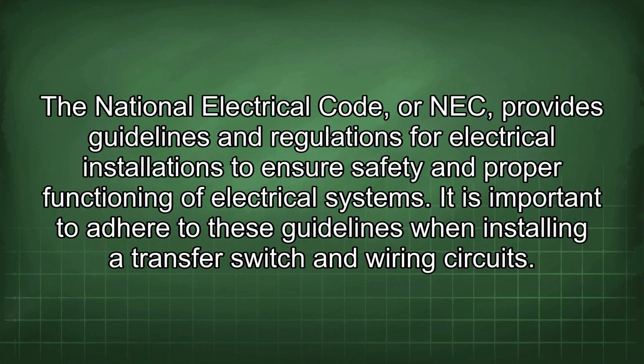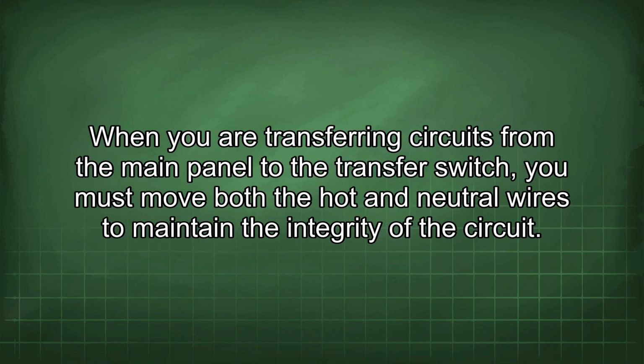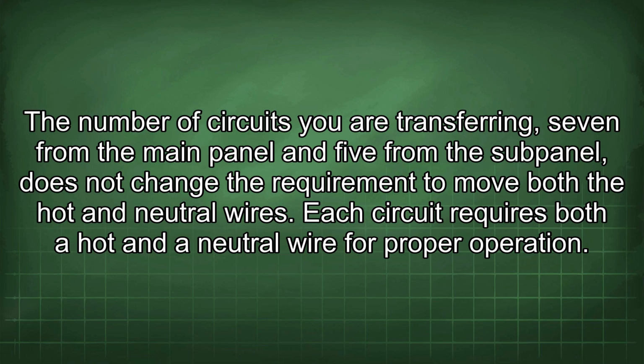The National Electrical Code, or NEC, provides guidelines and regulations for electrical installations to ensure safety and proper functioning of electrical systems. It is important to adhere to these guidelines when installing a transfer switch and wiring circuits. When you are transferring circuits from the main panel to the transfer switch, you must move both the hot and neutral wires to maintain the integrity of the circuit. The number of circuits you are transferring, 7 from the main panel and 5 from the subpanel, does not change the requirement to move both the hot and neutral wires. Each circuit requires both a hot and a neutral wire for proper operation.